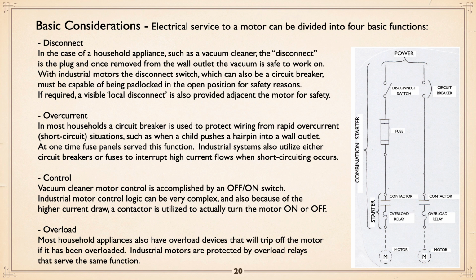And we go through the whole thing. In most households, overcurrent is provided by, now overcurrent is like a short circuit. A kid pushes a hairpin into a wall outlet or whatever. Bang, you've got very high current. That very high current you need to disconnect quickly. You've either got a fuse in your house or a circuit breaker. Nowadays, almost purely circuit breakers. And similarly, in industrial, you have to have either a fuse or circuit breaker to service that motor, so that in the event the motor shorts out, suddenly high current, you've got something to break that power supply quickly.